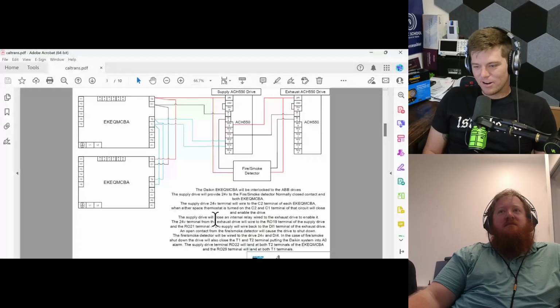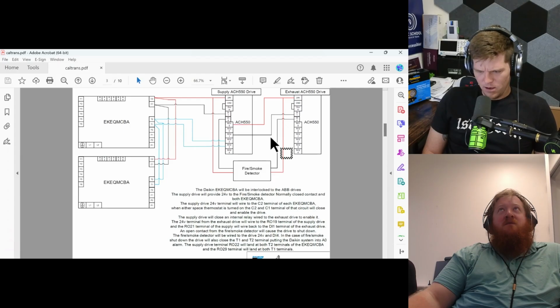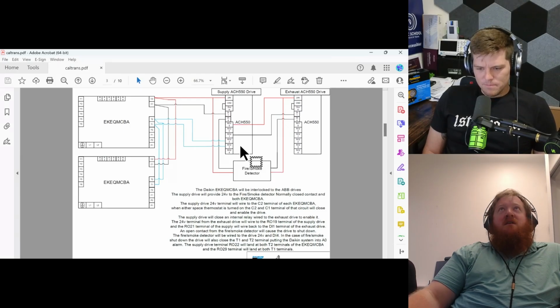I've seen it too, where we didn't break the life safety device - we installed the system, did the comm wiring, but a third-party contractor came in and said 'well this is their control wire,' and just snipped it. Then they daisy-chained in, and you find it later down the road and wonder why someone would do that.